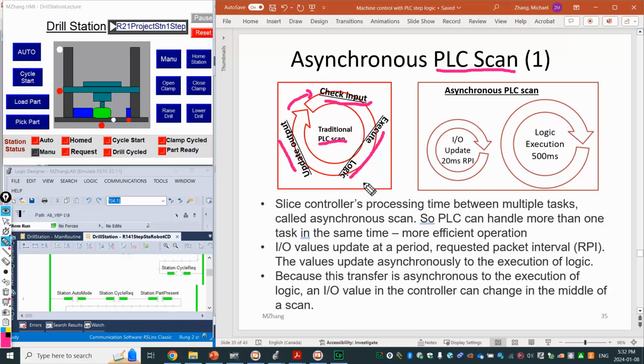For this type of scan, depending on the controller, it can run maybe a few hundred times a second, no problem - it also depends on how big your program is. With the regular lab setup we designed, the PLC controller can scan your program every second, maybe 500 or 600 times, no problem. That's a pretty decent setup with the traditional one.